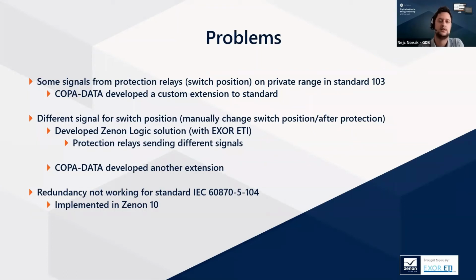The next problem was a different signal for switch position, depending on whether the switch was changed manually or changed by a protection relay. The first solution was to develop a Zenon logic solution together with EXOR ETI, which worked fine on one relay, but when we tested it on the whole substation, we noticed that protection relays were sending different signals, so this solution didn't work. The real solution was for Copa Data to develop another extension to add to that first one.